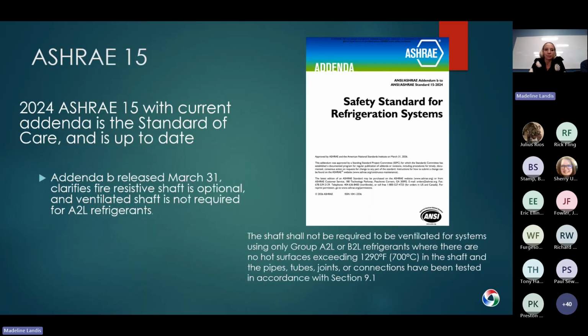So ASHRAE 15, again, one thing I wanted to point out specifically about that, maybe you've been hearing about this coming. Yes, addendum B is now officially out, which totally gets rid of both the trigger for a fire resistive rated shaft in the first place, and then having to ventilate that shaft. So this is a huge reason why we want to use ASHRAE 15.